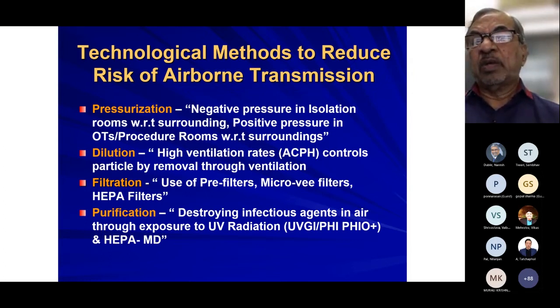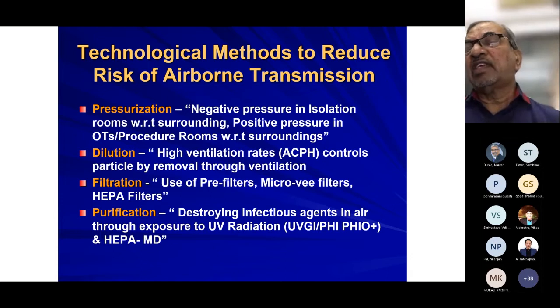Now second is dilution. You have a high ventilation rate, that is air changes per hour, which controls particles by removal through ventilation. During COVID, as IGBC chairperson for the healthcare rating system, we came out with guidelines on how to handle air quality during COVID-related issues.